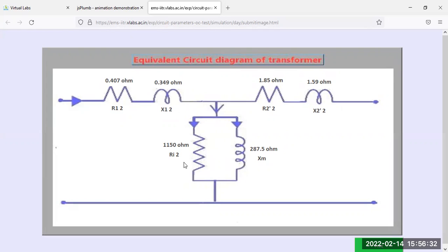Similarly, XM, the magnetizing reactance, equals 230 divided by 0.9 into sine phi 0. Sine phi 0 is the square root of 1 minus 0.0576. If you solve this numerically, 230 divided by 0.9 into square root of 1 minus 0.057, you get almost the value of 287.5 ohm.